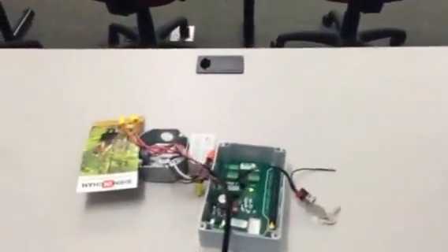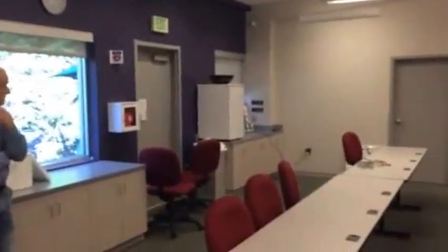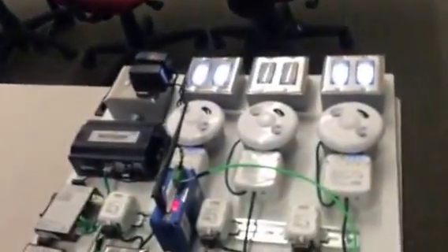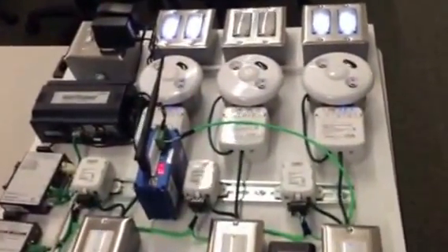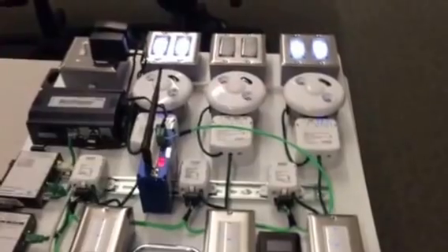So I want to walk through very quickly what's happening there. As Elliot controls that, activates that switch, that comes over to the segment manager, which sends the message across the Ethernet to the switch, to the bridge. It goes on RS-485 to the bridge, and then it sends it over to the remote building and controls devices in that space. Two different technologies that are very valuable to completing the applications to extend DLM from just wired solutions to wireless solutions to bring value to our customers.